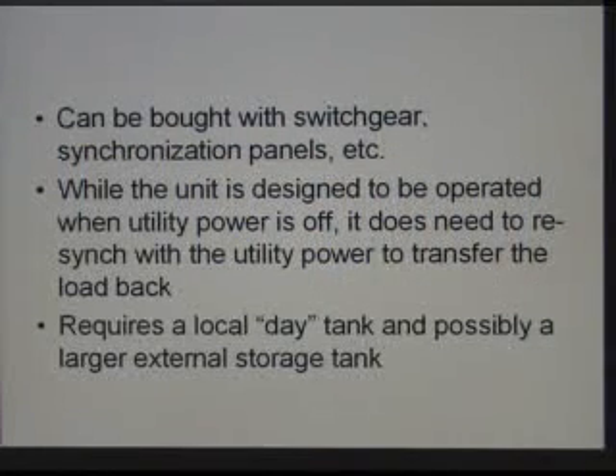Now as a package, we can get the genset with a control system which will do protection and monitoring of the engine and the generator, but we can also buy the package with the switch gear and the synchronization panels which allow it to be brought online to utility power if you should ever want to run this with utility power. And sometimes the operators and the owners like to do that so they can exercise the generator every month or so to make sure that it operates properly and that there's no carbon buildup inside of the cylinders.